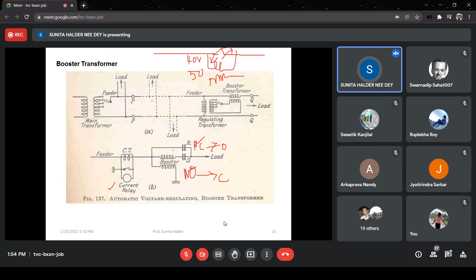Okay, the current relay actually operates when R is closed and AC is open. Normally, R is normally closed and AC is normally open. Now, when the current relay operates, then R gets open and AC gets closed, then the booster transformer comes into operation, right?